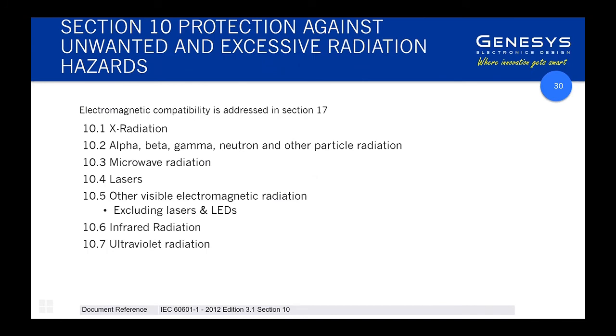Section 10 is specific to devices that intentionally generate radiation — generally X-ray machines — and includes lasers. This won't normally apply to most equipment. However, quite a few devices do have lasers, so if you're using a laser for a ranging or indication function, you may have to deal with laser safety requirements under this section.